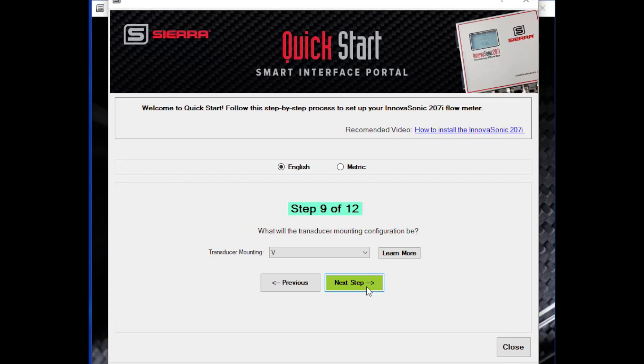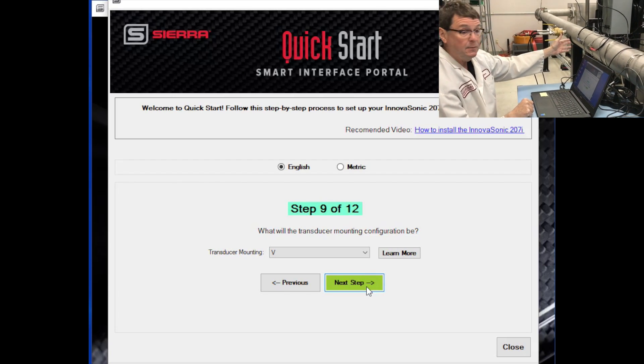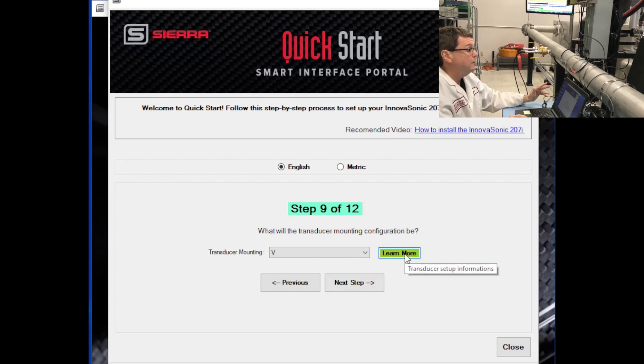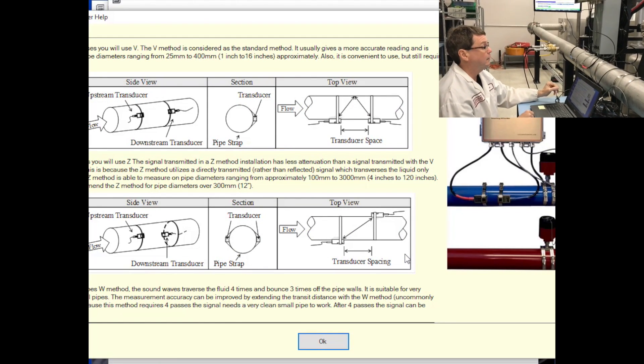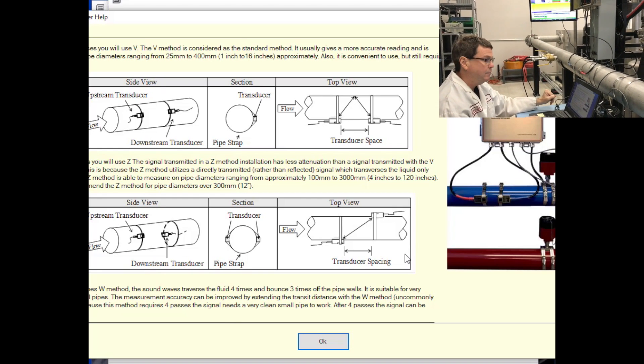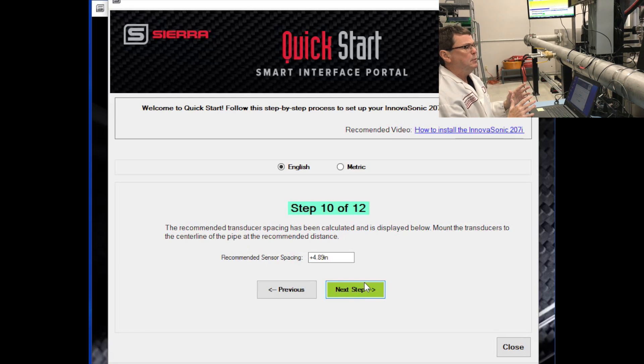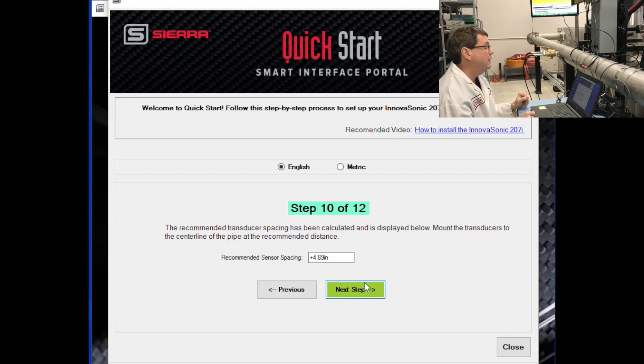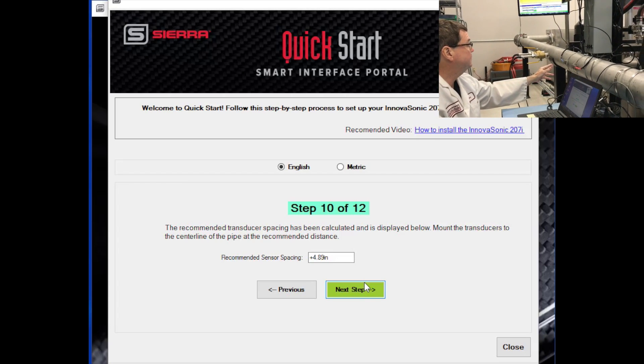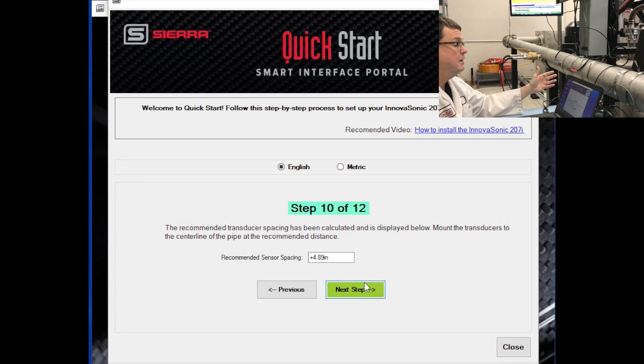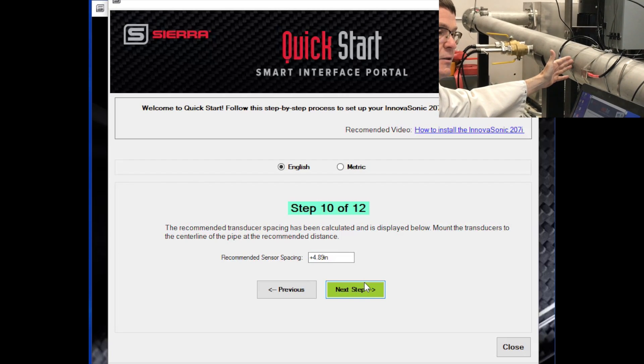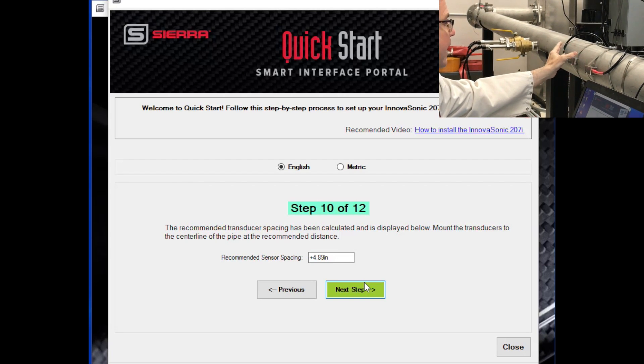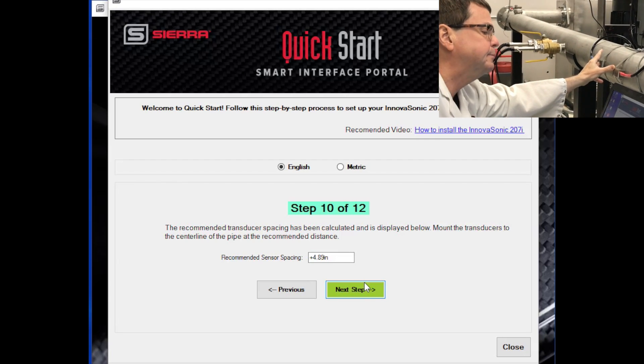Step nine is what transducer mounting configuration are you using? There are various methods to mount the transducers on the pipe. What I have here is a V-mount, but there are other ways to do that. You need to tell the meter what you're using. If you want to learn more about what those types of mounting methods are, you click on the Learn More button, and it will tell you the various mounting methodologies that you can use. In this case, we'll use V-mount. And the next step, the meter will consider all the information that we've just inputted and tell you how far apart to space the transducers. In this case, the recommended sensor spacing is 4.89 inches. So I would essentially take a ruler and measure from the face of one transducer to the face of the other and approximately make that measurement 4.89 inches, get as close as I can.